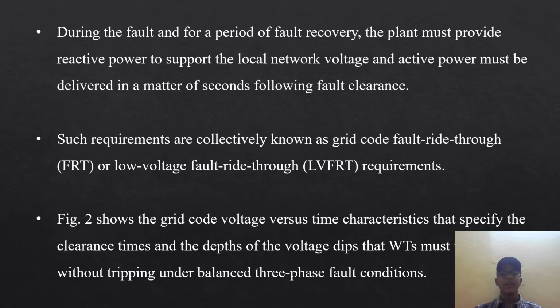During the fault and for the period of fault recovery, the plant must provide reactive power to support the local network. Voltage and active power must be delivered in a matter of seconds following fault clearance. Such requirements are collectively known as the grid code fault ride through or low voltage ride through requirements.